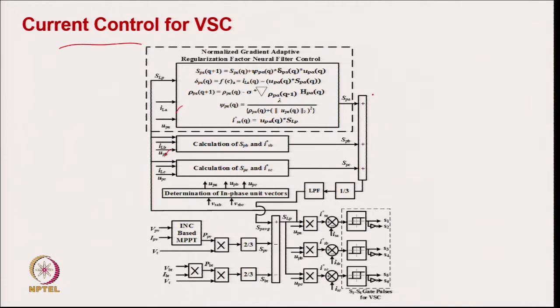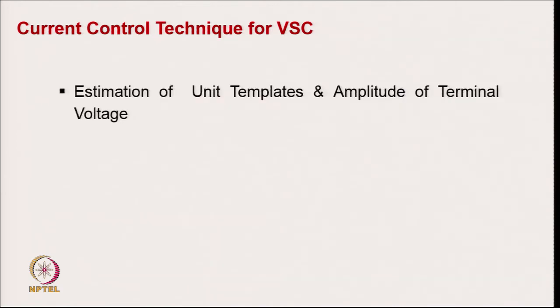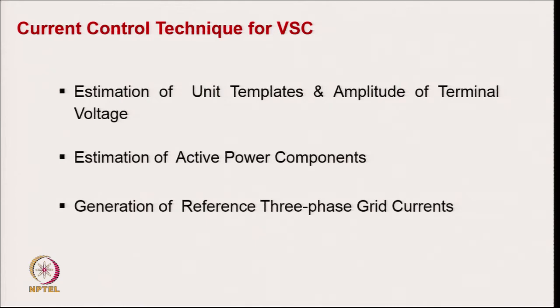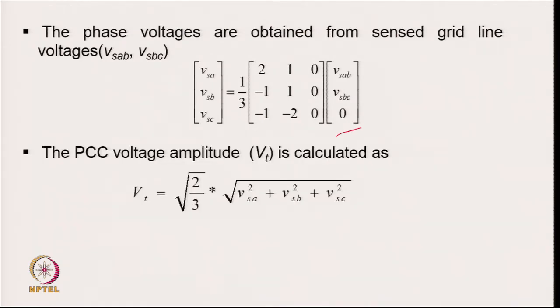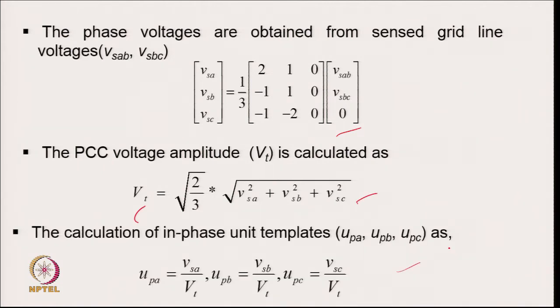In grid-connected mode we use current control. We sense the load and extract the fundamental component of the load current, then calculate the template from the sensed line voltage and phase voltage. We have the maximum power feed-forward term and the battery component for power exchange. This gives us the amplitude of the grid current. With the template, we generate a reference grid current and compare it with the sensed grid current to control the converter, improving power quality on the grid side.